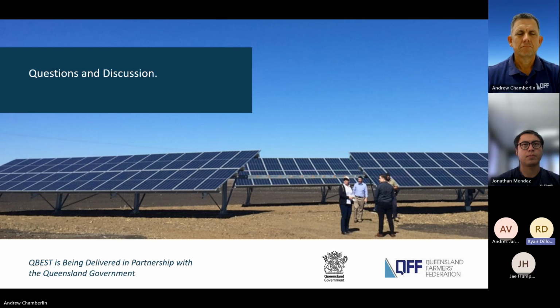So that ability to use a heat pump, some of the heat pumps from Apricus, for instance, have basic logic that says turn on between this time and this time. And some of the more advanced heat pumps for hot water systems, thinking of this heat storage, can actually communicate with solar, where you've actually got export energy. There's some logic to say, okay, heat the water now, or don't because the solar's not running or it's cloudy. A little bit more expensive, about a couple of grand difference for a residential scale heat pump. So I think it's an opportunity. You just really need to manage it and monitor it and know what you're doing. And that can all be addressed through an audit.